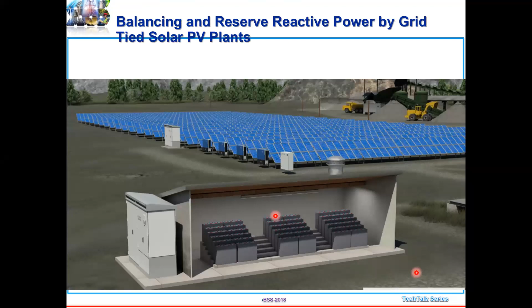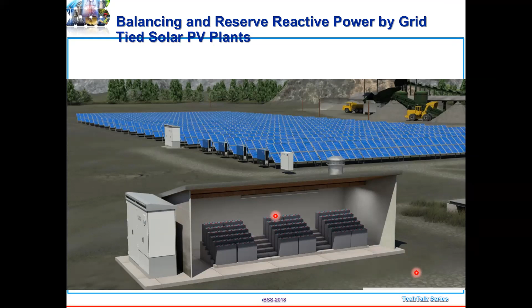This is what we actually tried, in Ambalatara. When we had a real shortage of reactive power during the crisis in summer, we insisted, because there's an ABB make reactive inverter system, a 1000 kVA, 1 MVA reactive inverter, which has reactive power capability, day and night, because almost all current inverters are basically voltage source inverters, current controlled voltage source inverters. So you can easily provide support, because they have a DC system in the background for controls, for stabilizing the DC bus, with capacitors. They can use this capacitor system to provide the required reactive support to the grid.